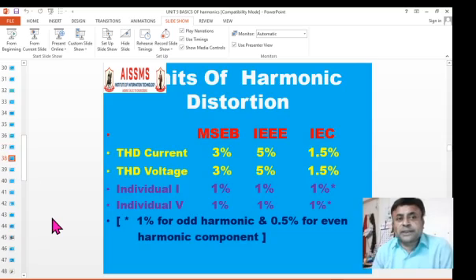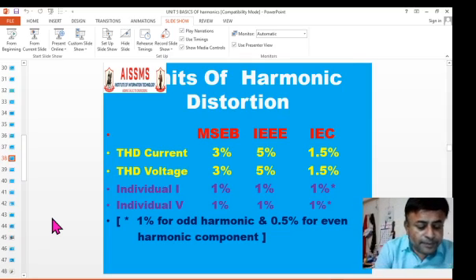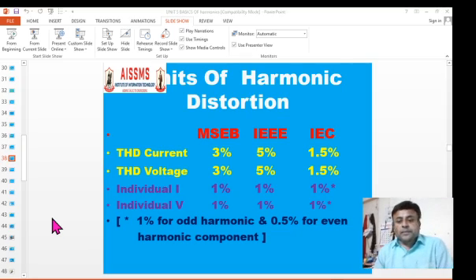So to control these limits, statutory bodies like IEEE, MSEB and IEC have given certain guidelines. As per these guidelines, THD, that is total harmonic distortion, is the basic parameter for giving limits of harmonics. It is 5% as per IEEE, 3% as per MSEB, and 1.5% as per IEC, that is International Electrotechnical Commission.